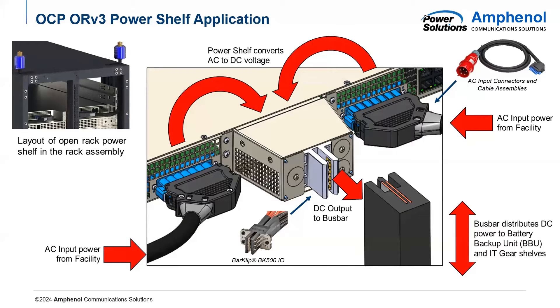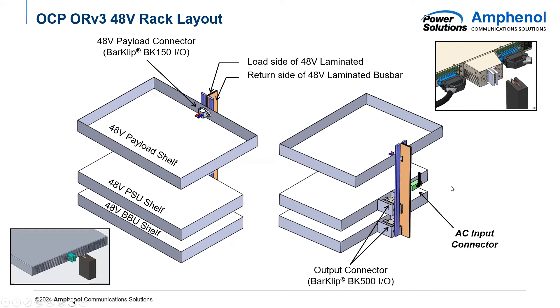This is a great example of what a power shelf does within a data center. It takes AC power from the facility using our AC whip cables and inputs it into the power shelf. The power shelf's PSUs convert the power from AC to DC and make it 48 volts, which is what an ORV3 power shelf uses, and puts it onto our BarKlip BK500 connector, which would then power the entire bus bar running up the back of the rack. In some diagrams there will be one AC WIP connector, but oftentimes you will see two, depending on how much power they need to input.